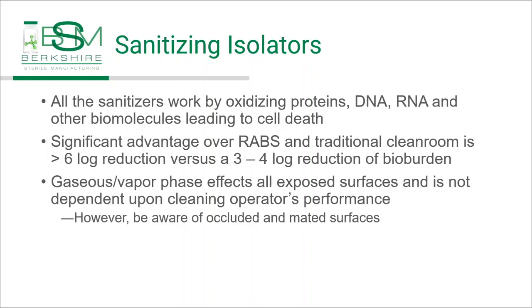However, you do have to be aware of occluded and mated surfaces. Materials have to be hung in such a way that there's enough space in between them for the gaseous vapor to get to them and cause the sanitization. And large objects which may be mated to the floor may have to be lifted up off of the floor with basically dollies or round cylindrical tubes, so the sanitizing solution can get underneath.